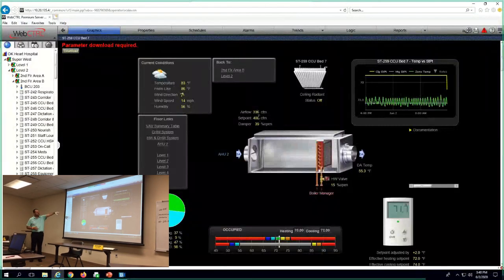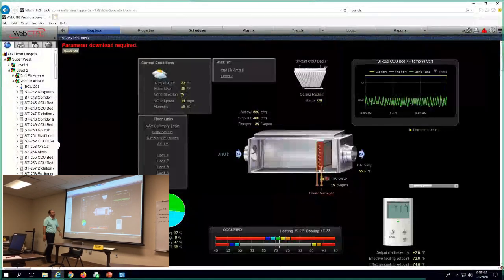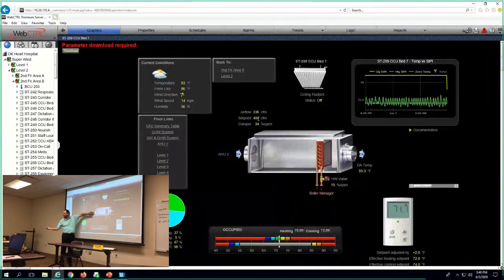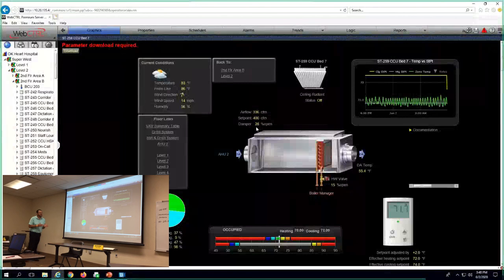So you can see the set point changed to 400 CFM. That VAV damper should start opening up. We're measuring again the velocity pressure at the end of the VAV, remember? It's going to measure that airflow and then should start opening up. We're not too far away from set point, but it will gradually start trying to get there. So that's one. Let's jump back over there, Joe.